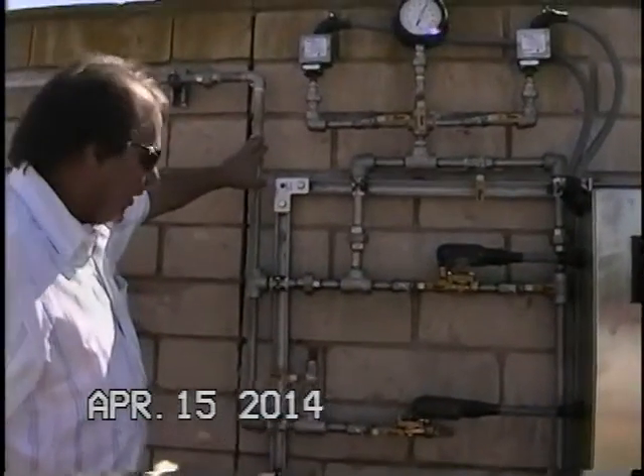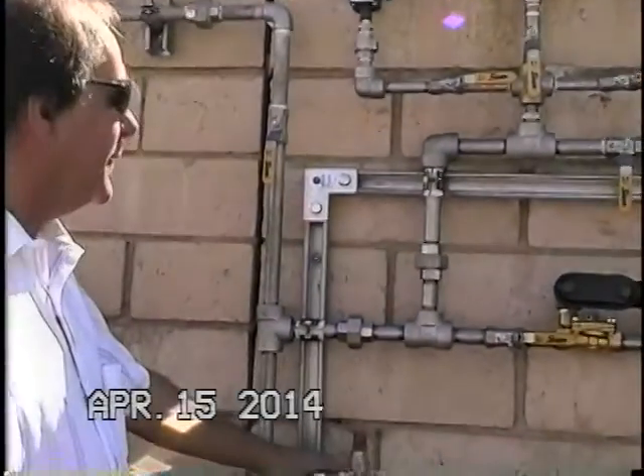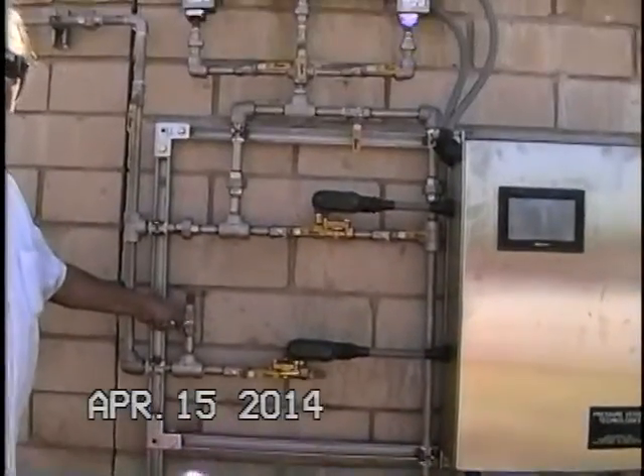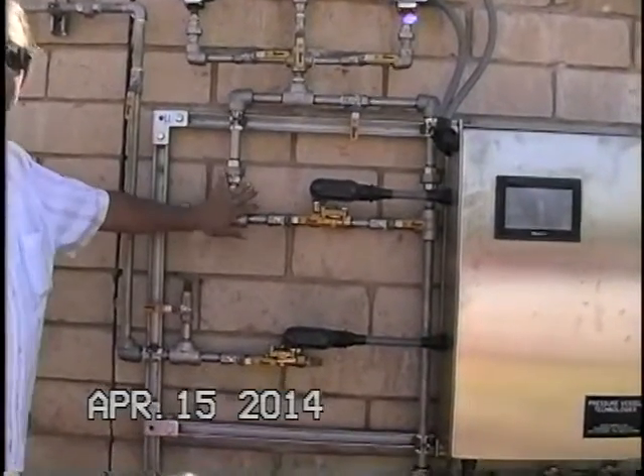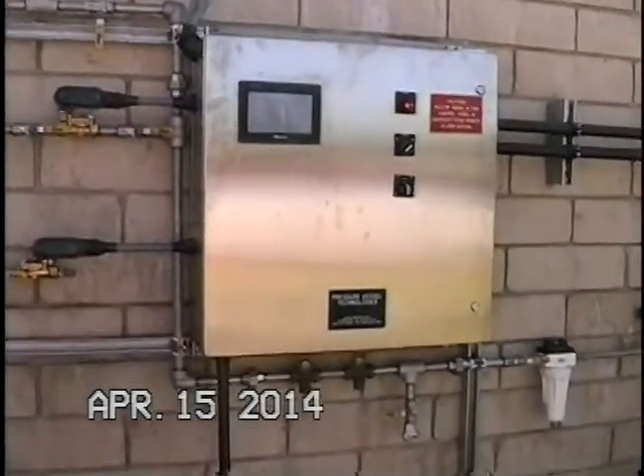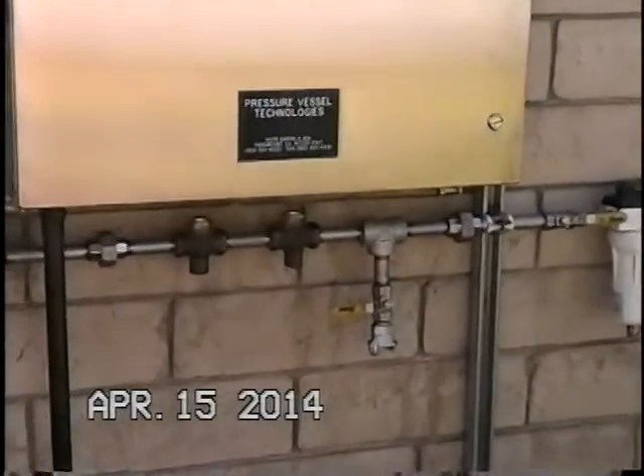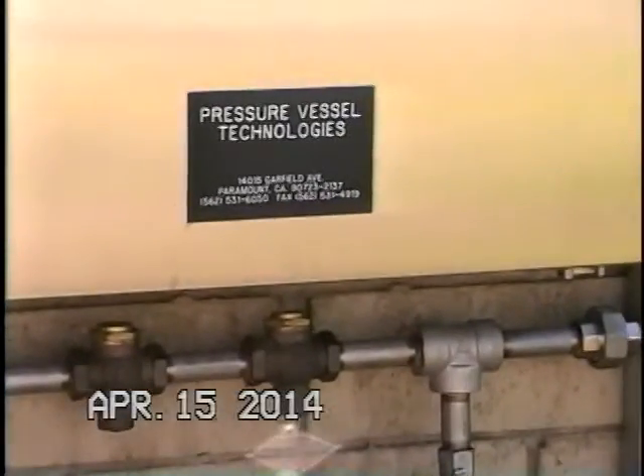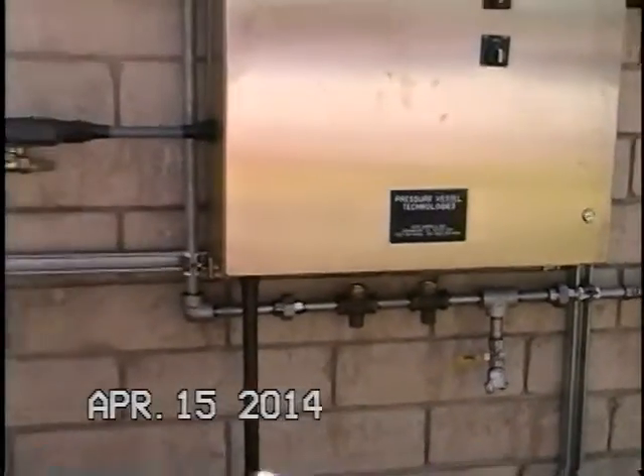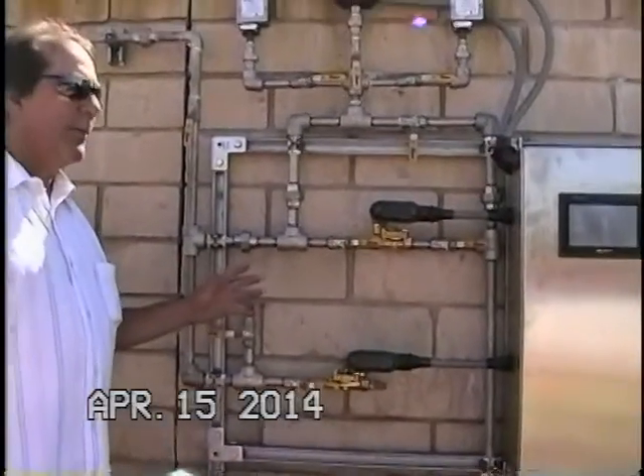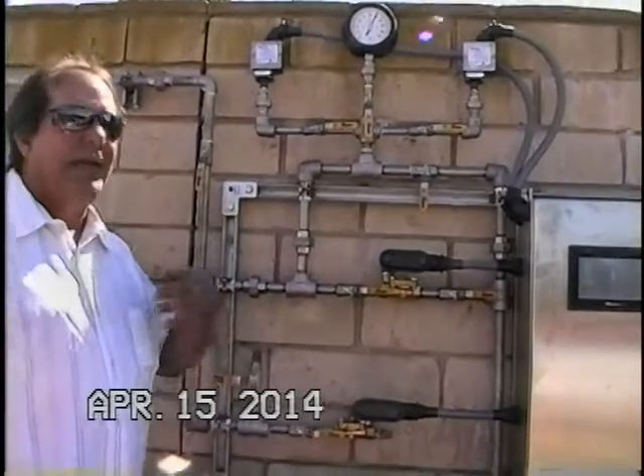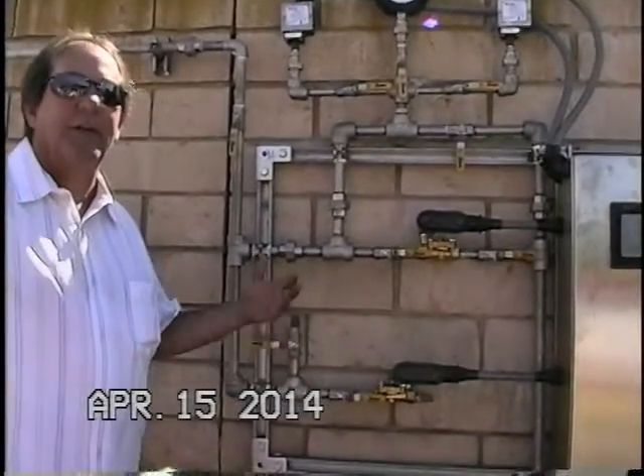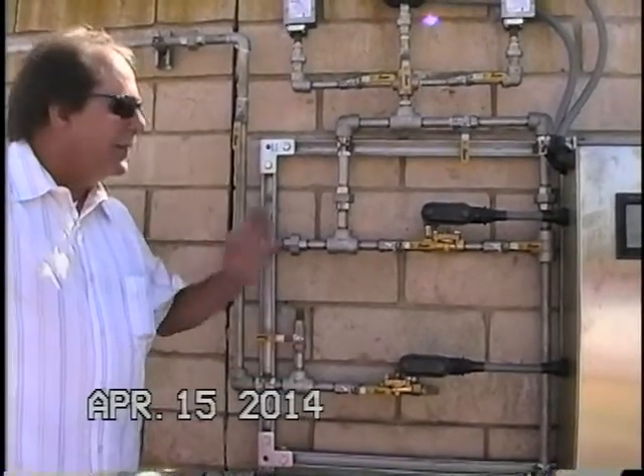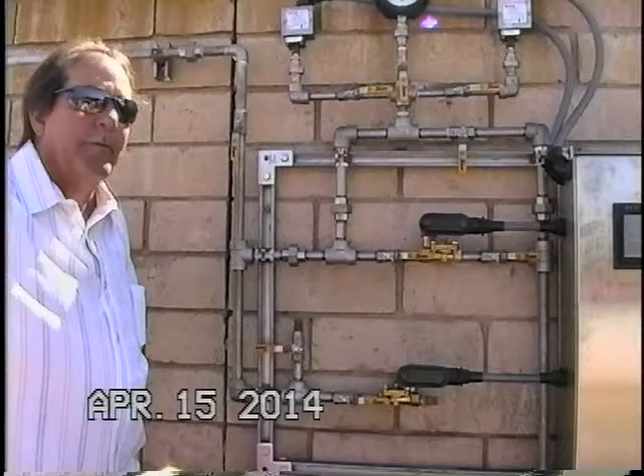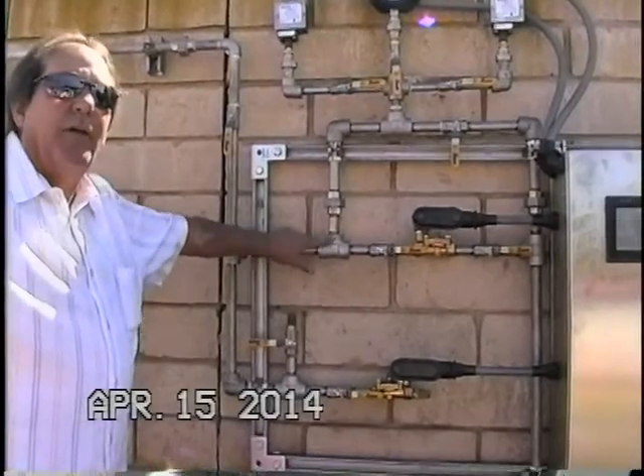You've got an isolation valve here, and then you can vent. Once you isolate both the inlet and the outlet, you can vent the air, and that would completely depressurize your air volume control piping. So you have the ability to isolate it and work on it. If you had a leak, stainless piping is notorious for leaks. Typically, once you get them sealed, you're pretty good. But in an outdoor application where you've got heating and cooling, summer to winter, this expansion and contraction of the material sometimes will give you a leak. You may have to go ahead and do it. Any questions on air volume control piping?